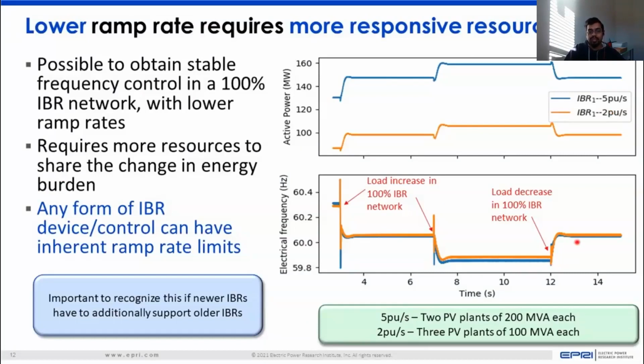And what that means is that the sharing of the energy burden now needs to be socialized across a number of resources. But supposing you already have a large number of legacy devices that are inherently limited by these ramp rate constraints or are not designed to provide these kinds of frequency response services, then it's important to recognize that as more newer inverter-based resources come into the system, they would have to take up an additional burden of what the older resources would have to provide. So if you had traditional inverter-based resources at, let's say, 2 per unit per second, which cannot provide a frequency response service in a system with increased inverter-based penetration, then the newer inverter-based resource coming in should not be at 2 per unit per second, but rather it might have to be at 5 per unit per second or even 10 per unit per second, so that it can take on that additional burden.